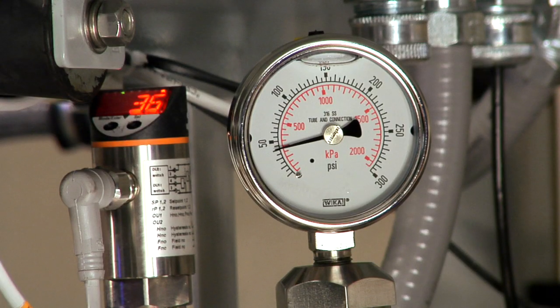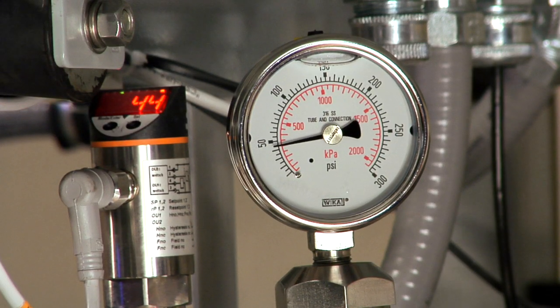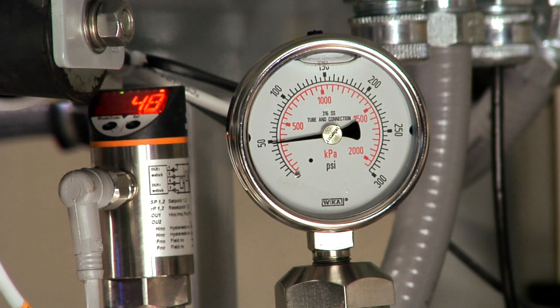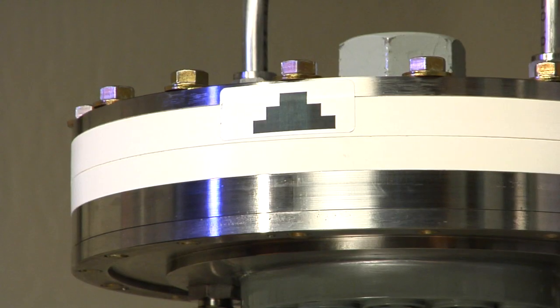At this point, the pressure should be between 30 and 60 psi on the outlet pressure gauge. Once you are above 30 psi, start vibration by pushing the green start button one more time.